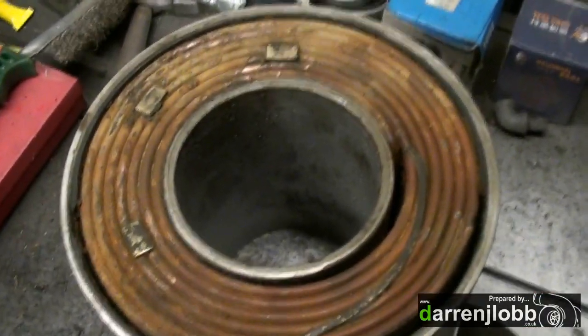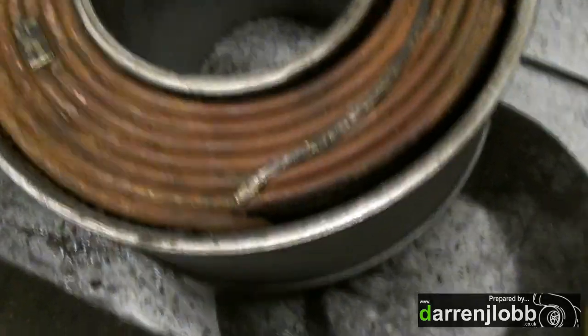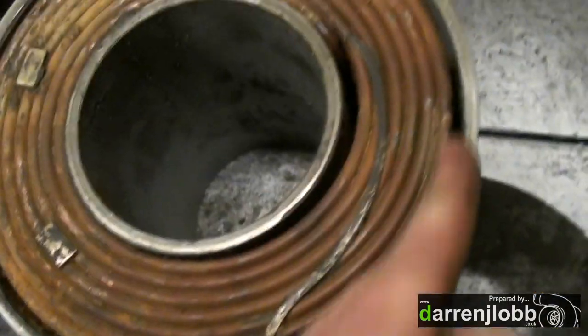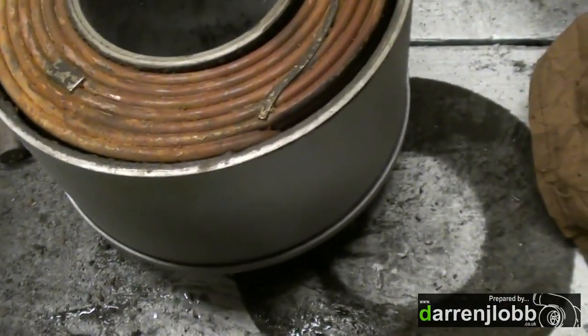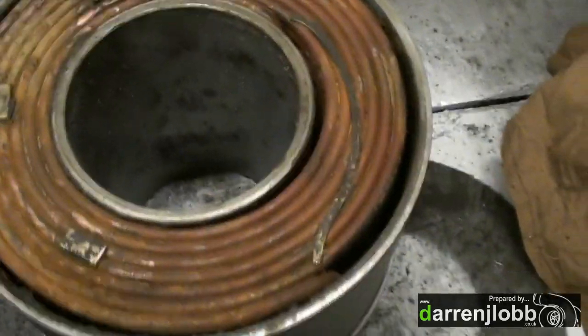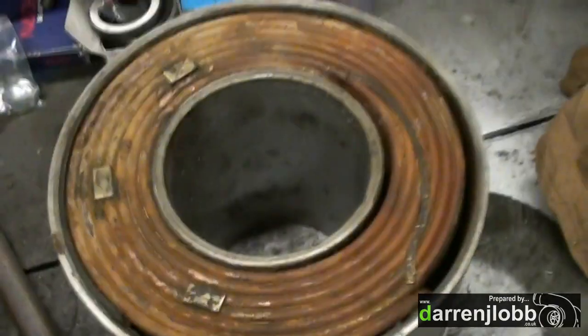So this is the other side of the heat exchanger now. This one's actually in very good condition - no pitting to the actual copper tubing at all. This is where the heat is exchanged from the water that circulates around the brake, and the water that goes through the cooling tower, because all the energy is made into heat. You can see where the water flows in here and flows out there, and the water from the other end is coming from the tank, which is inside the coils. It's just a basic heat transfer process. So I've just cleaned that up a bit.